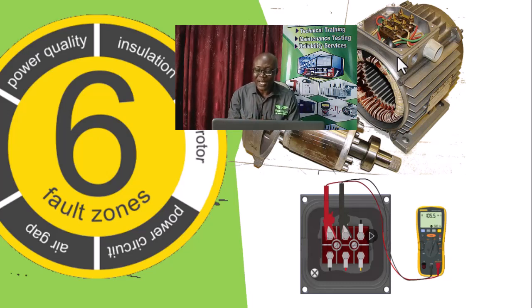Okay, so if we remove those bars, we can test the insulation between the U phase, the V phase, and the W phase. Are we getting it? U, V, V, W, and W, U. Usually we expect the insulation to be high. If we are looking at a low voltage electric motor, 10 meg is okay. But if we are looking at a medium and high voltage electric motor, 100 meg is okay. But even at the low voltage electric motor, we need the insulation resistance to be very high. The higher the insulation resistance, the better for us.